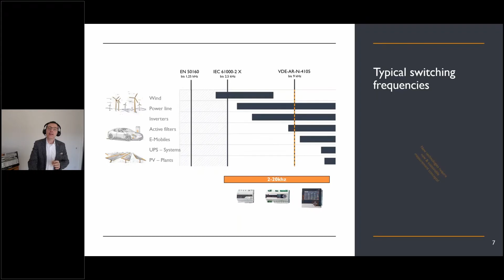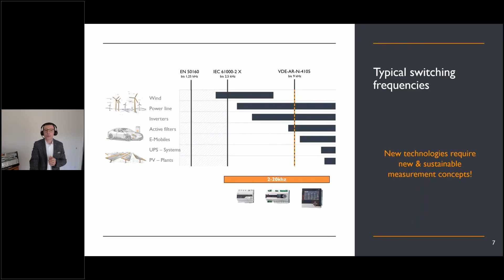So it's necessary for an Eberle product, especially in the low voltage grid, to support these new standards and requirements with sustainable measurement concepts. This doesn't mean higher harmonic measurement is necessary in every case, but there must be an opportunity to add that higher frequency measurement concept to the device. Therefore we provide a license model where for every product you can add the technology needed for measuring the so-called supraharmonics.